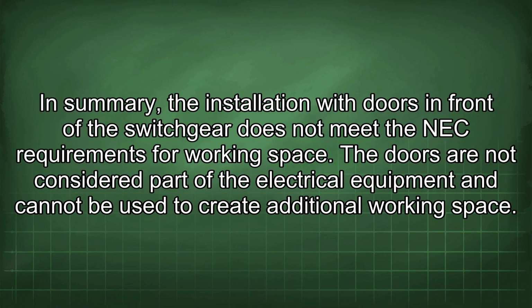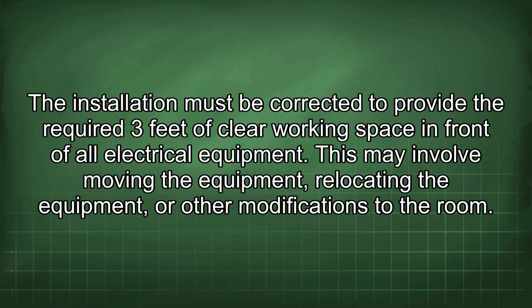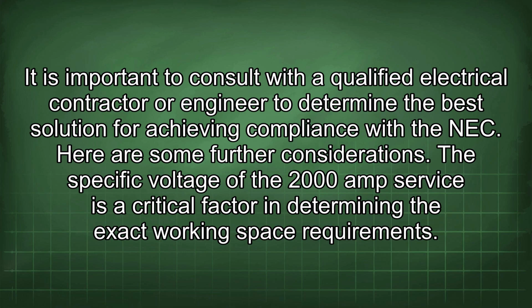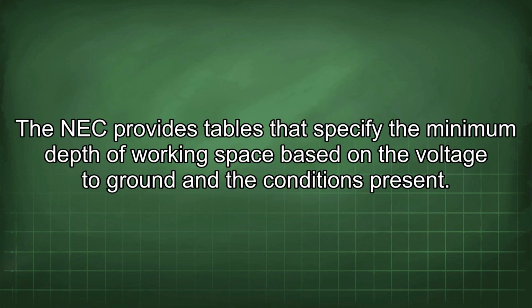In summary, the installation with doors in front of the switchgear does not meet the NEC requirements for working space. The doors are not considered part of the electrical equipment and cannot be used to create additional working space. The installation must be corrected to provide the required 3 feet of clear working space in front of all electrical equipment. This may involve moving the equipment, relocating the equipment, or other modifications to the room. It is important to consult with a qualified electrical contractor or engineer to determine the best solution for achieving compliance with the NEC. Here are some further considerations. The specific voltage of the 2000 amp service is a critical factor in determining the exact working space requirements. The NEC provides tables that specify the minimum depth of working space based on the voltage to ground and the conditions present.